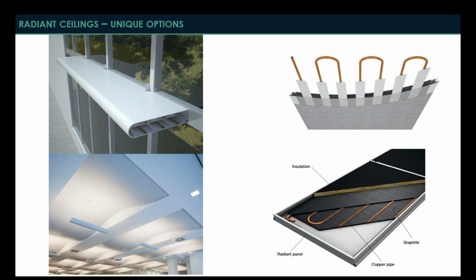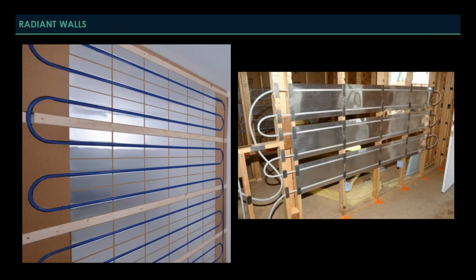And in the bottom right corner, there's a type of modular panel that is a little bit different in that the copper tubing is not attached in the same way that you would find with a lot of modern radiant panel designs. The copper tubing is actually set in graphite, and the graphite is then thermally bonded to the steel panel. And what this does is really try to increase the effectiveness of the heat transfer from the copper tubing to the radiant panel. And the ultimate benefit there is that these panels can be a slightly higher capacity than a traditional aluminum radiant ceiling panel.